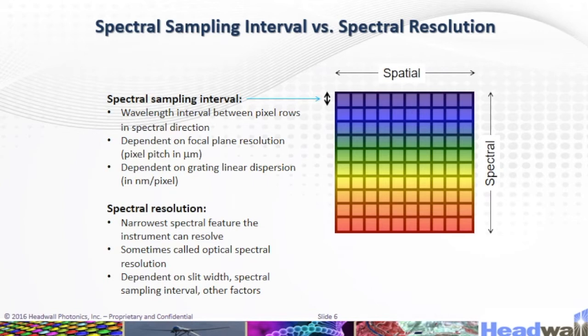Here we have the spectral sampling interval (SSI) versus spectral resolution. The SSI parameter is related to geometric spacing, dispersion, and other factors. Optical spectral resolution is usually broader than SSI. For example, with a 20-micrometer slit and 6.5-micrometer pixel pitch, the slit equals approximately 3 pixels. The spectral resolution is therefore approximately 3 times the SSI, plus a little more due to other optical factors.